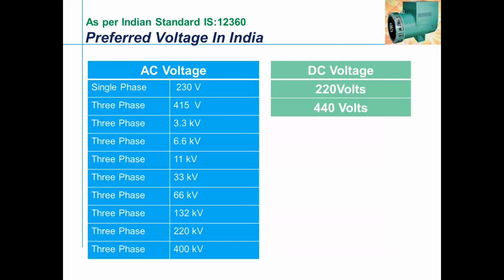And there are a lot of preferred voltages in India. In single phase, most domestic household items use 230 volts. Of course, in commercial buildings and apartments, people prefer three phase, 415 volts. Where the input supply goes beyond 1 megawatt, people go for 3.3 kV and 6.6 kV. In case of long distance transmission, the higher the voltage, the lower the voltage drop, so higher voltage is used. It goes up to 400 kV, but in generators, we limit it to 11 kV. There is a reason for that, which we can bring across when we talk about insulation.